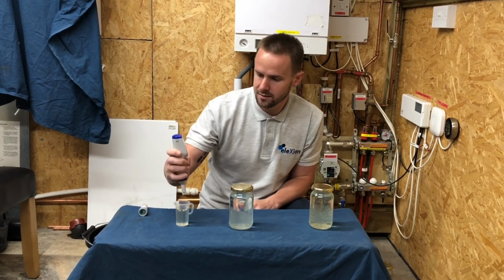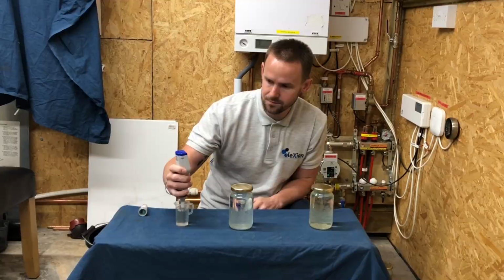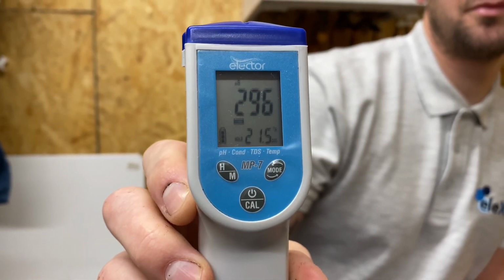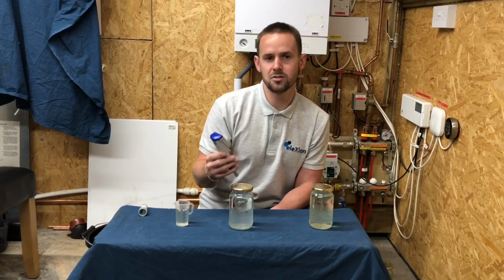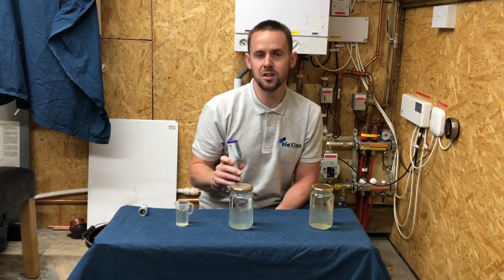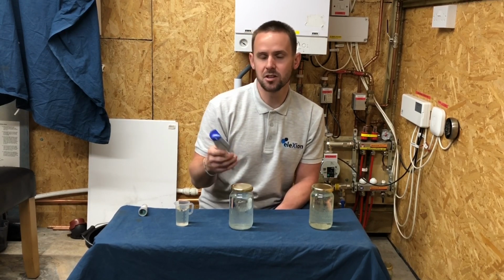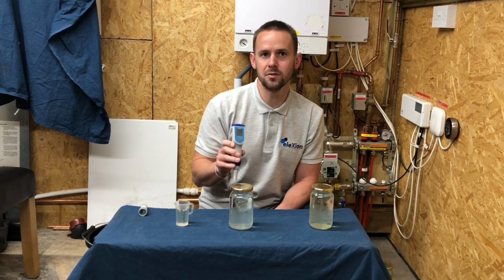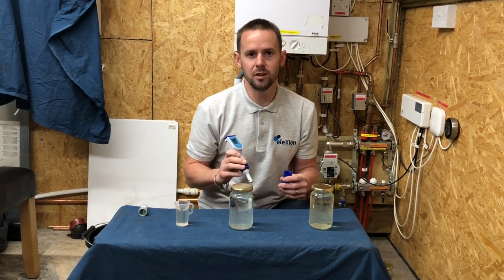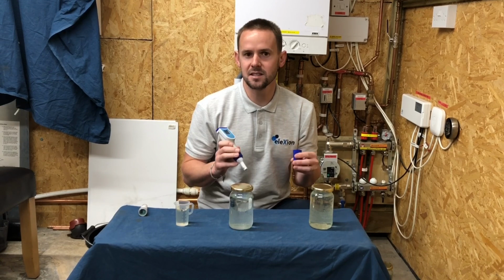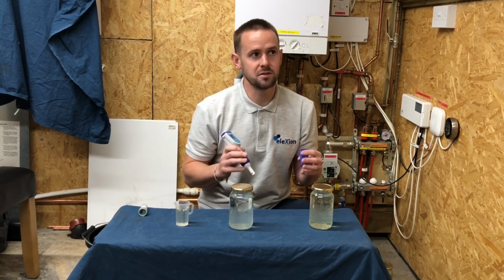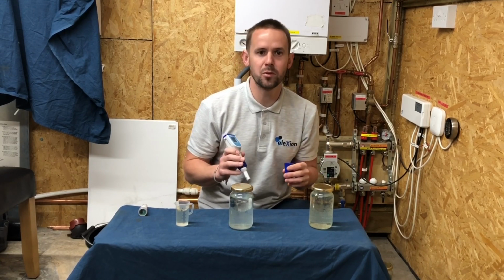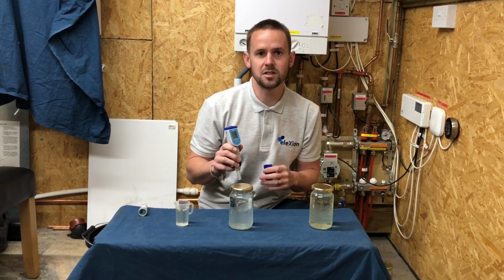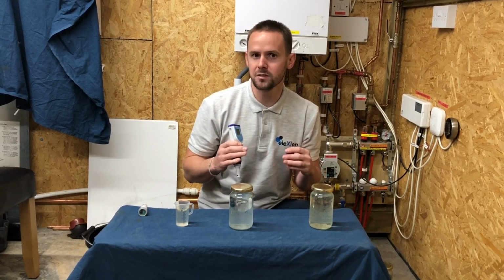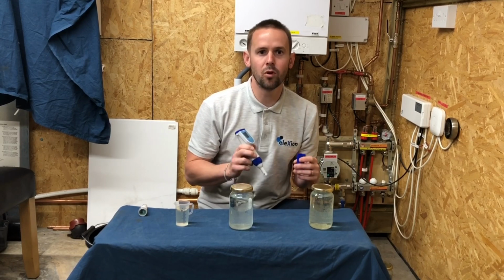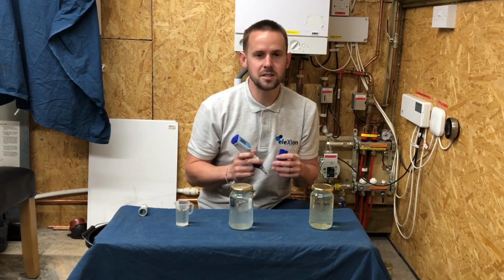I've got my pen again, just going to put this in. It's come out at 296 microsiemens. That's rather interesting because the tap water we tested originally was 198. So it's increased by 100 by having a bit of residue there from the cleaning agent. It's really important when we're doing our testing to make sure that we get all the system flushed properly and remove any chemical that we might have put in, because otherwise it is going to increase the conductivity, and what we want is a low conductivity. So it's really important to test before and test afterwards, and basically test during your flushing.